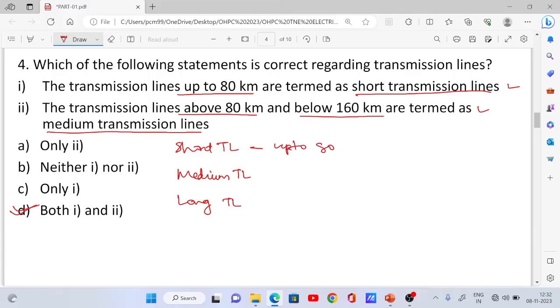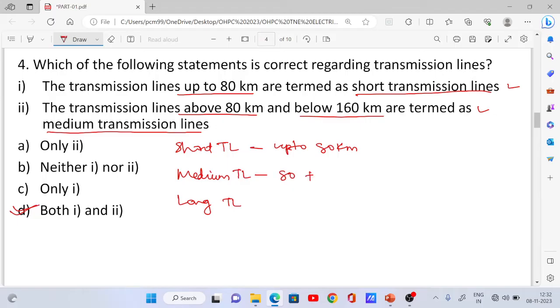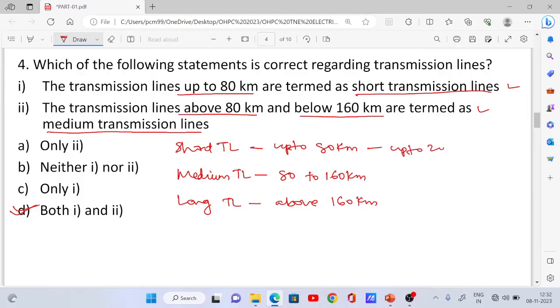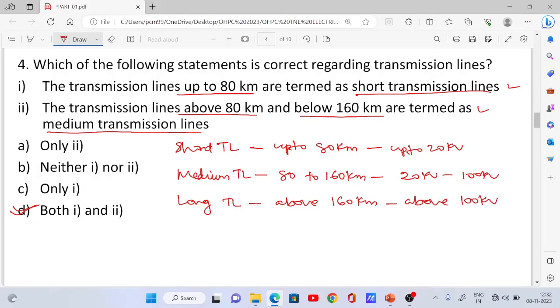Important classification: short transmission lines are up to 80 km, medium transmission lines are 80 to 160 km, and long transmission lines are above 160 km. Voltage levels: short lines up to 20 kV, medium lines 20 kV to 100 kV, and long lines above 100 kV.